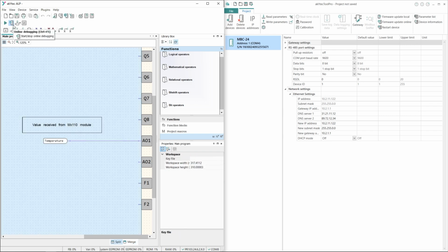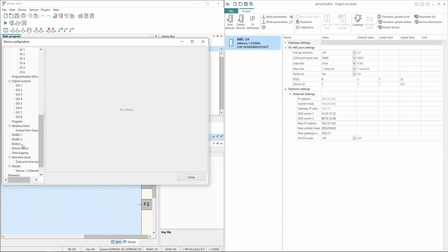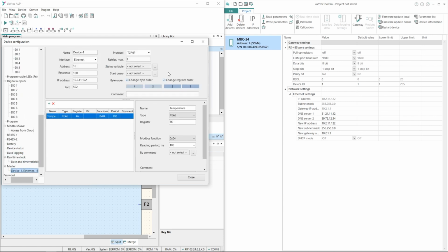But wait, there is one thing that we have not pointed out which is very important: byte and register order. As you saw on the MBC itself, we have not specified those orders. The reason is that the MBC just copies bit by bit and passes it. The MBC does not use that data, so it doesn't need to know the data's order. However, the end devices must have matching configurations, so pay attention to this point. This was our first case.